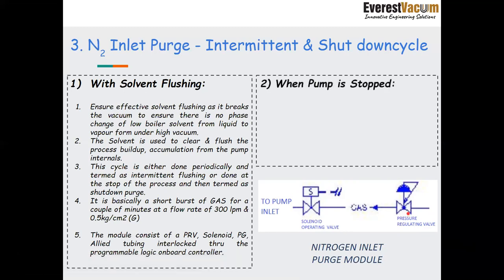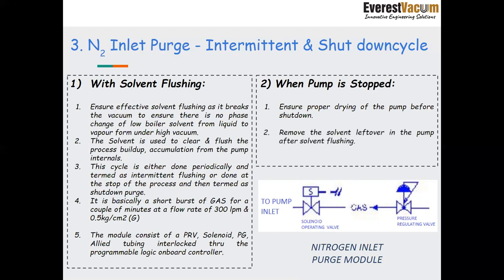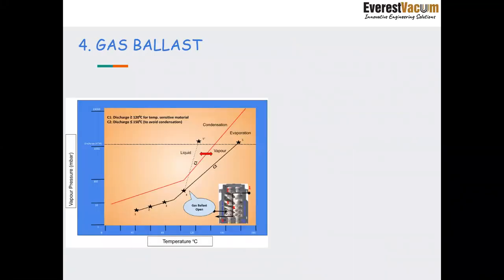And the other variant of it comes into play when the pump is stopped. At that time it ensures that the pump is completely dry. There are no solvent traces left in it. This is the purpose. It removes the solvent left over in the pump after the solvent flushing. Another module that Everest comes up with is the gas ballast module.